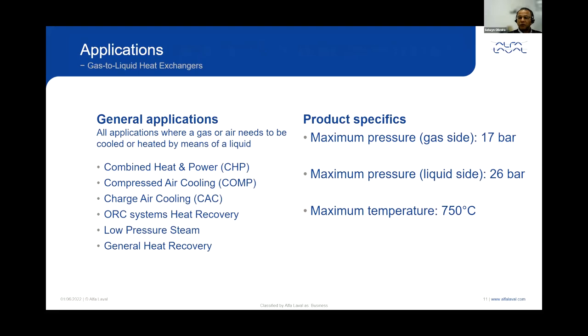They can be used for a multitude of applications. All applications where a gas or air needs to be cooled or heated by means of a liquid. Some of these applications are combined heat and power, compressed air cooling, charged air cooling, organic Rankine cycle systems, heat recovery, low pressure steam, general heat recovery, etc. Regarding the product specifics, the maximum pressure on the gas side is around 17 bar and on the liquid side, 26 bar. The maximum temperature 750 degrees C. However, we can offer some special units that can handle gas temperatures up to 1000 degrees C.